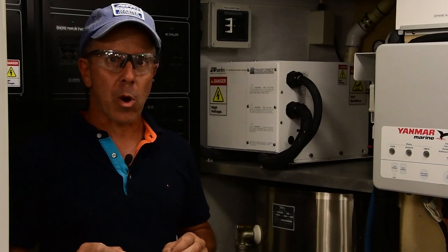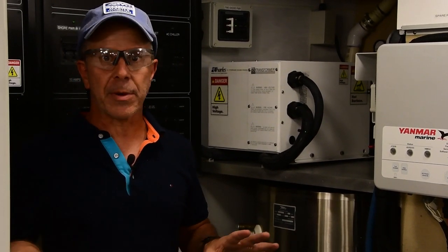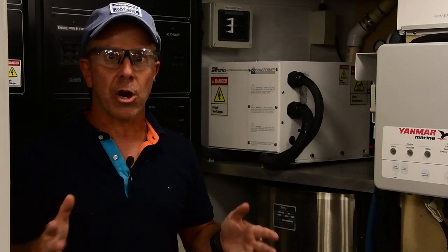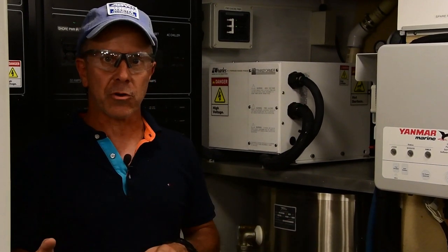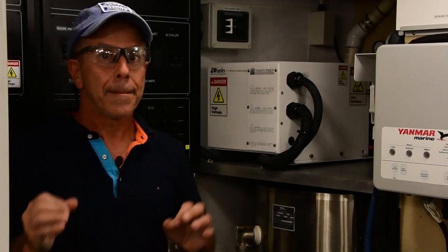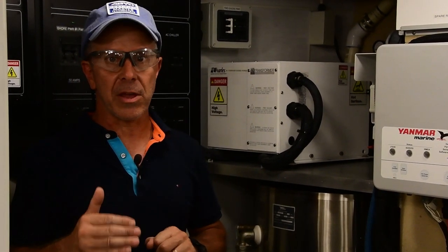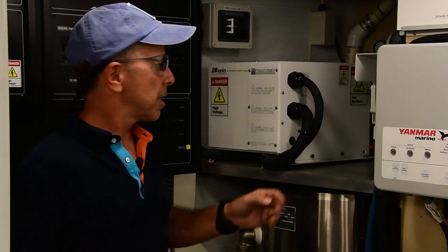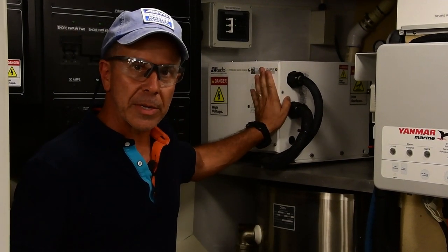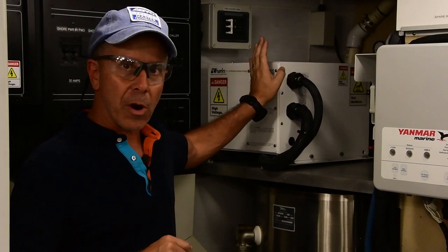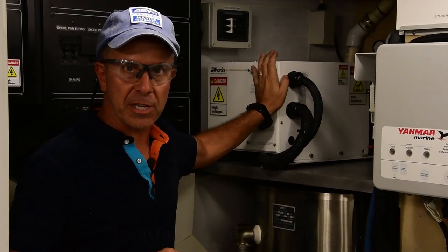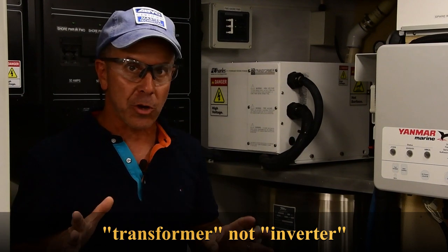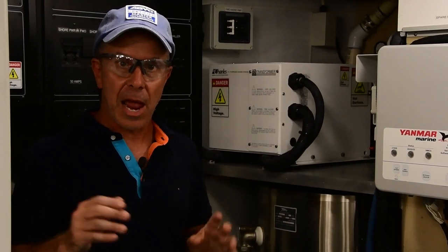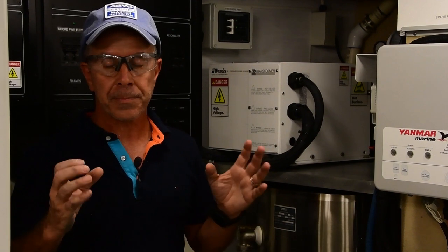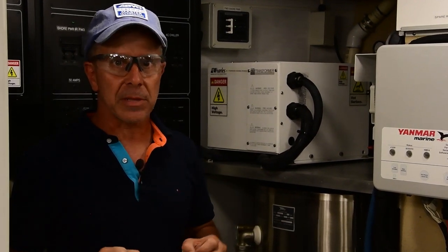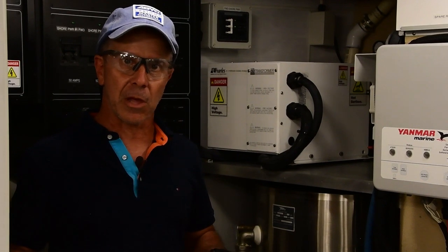If the transformer is wired for isolation, that common ground is no longer there because we are isolating the dock ground from the boat ground for all the reasons I mentioned earlier. But when you do that, it does elevate the risk slightly because the grounds are no longer common. So it's possible for an energized wire to make contact with the chassis of the inverter or the enclosure and not trip a circuit breaker and have it energized and present an electrocution hazard. Now, if the transformer is wired properly, the likelihood of that happening is extremely low.